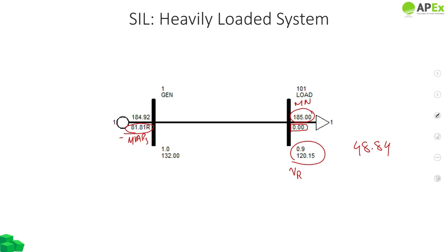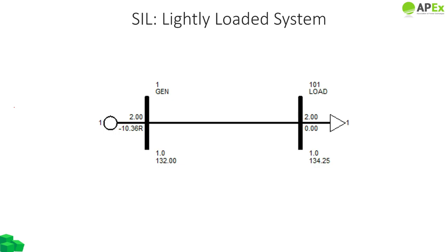Now this is an example of when a line is loaded above its surge impedance loading. So in the next example, we will reduce the loading of this particular line drastically and we will see what happens. In this case, we have a load of 2 megawatts being passed by this 132 kV transmission line. What we can see here is that the load is resistive and therefore does not consume any megavars.